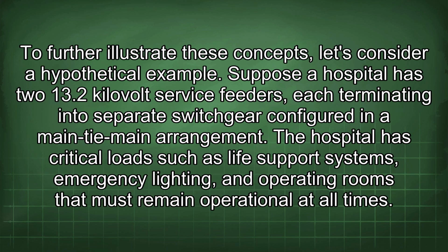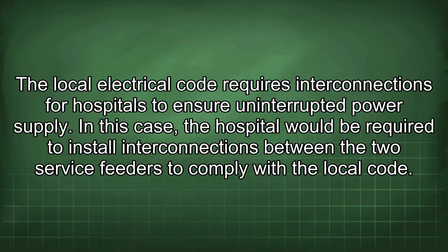To further illustrate these concepts, let's consider a hypothetical example. Suppose a hospital has two 13.2 kilovolt service feeders, each terminating into separate switchgear configured in a main tie-main arrangement. The hospital has critical loads such as life support systems, emergency lighting, and operating rooms that must remain operational at all times. The local electrical code requires interconnections for hospitals to ensure uninterrupted power supply. In this case, the hospital would be required to install interconnections between the two service feeders to comply with the local code.